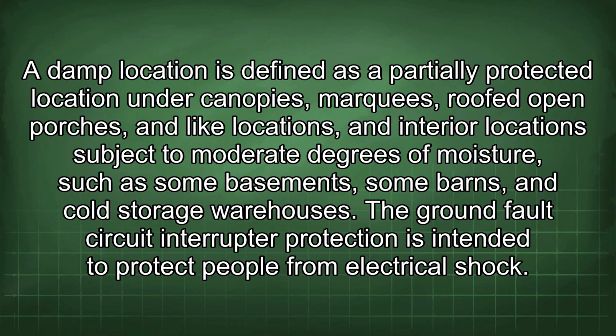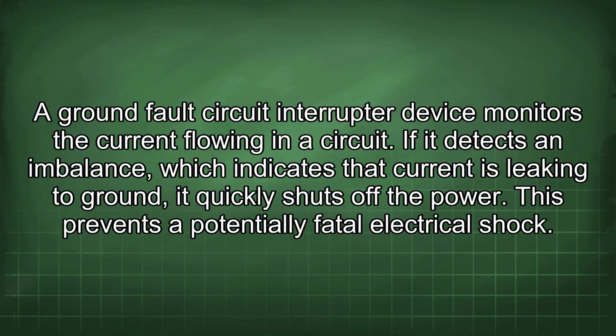The ground fault circuit interrupter protection is intended to protect people from electrical shock. A ground fault circuit interrupter device monitors the current flowing in a circuit. If it detects an imbalance which indicates that current is leaking to ground, it quickly shuts off the power. This prevents a potentially fatal electrical shock.